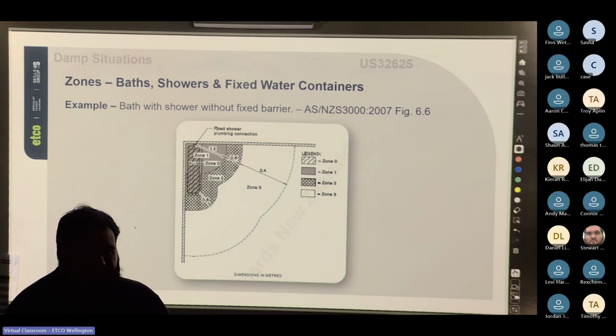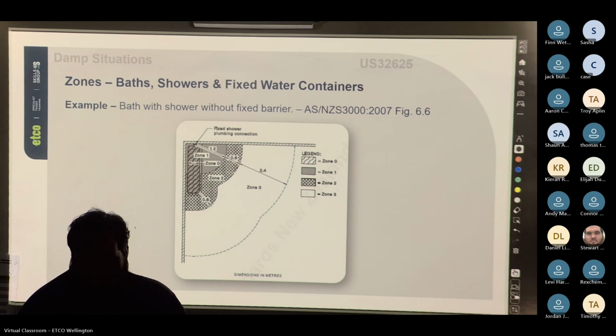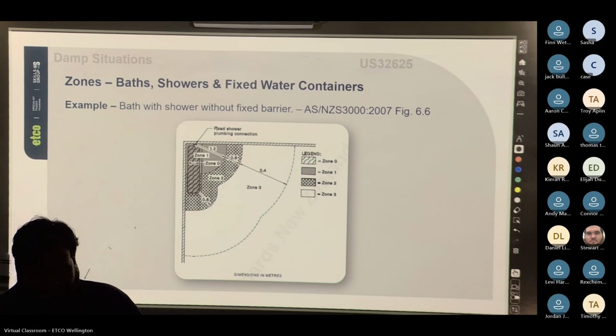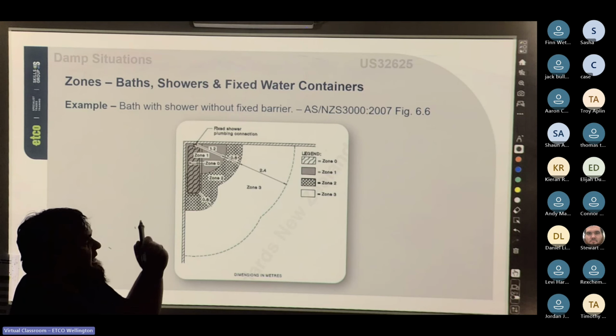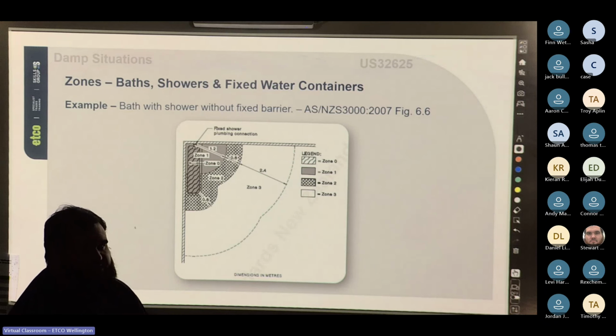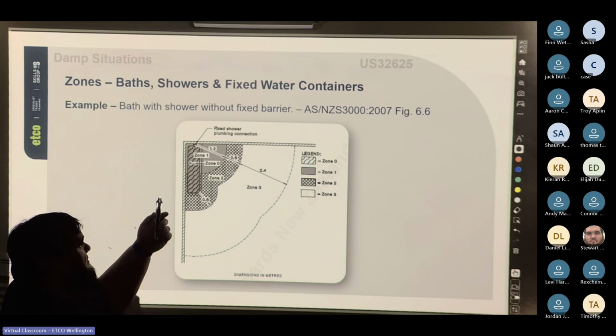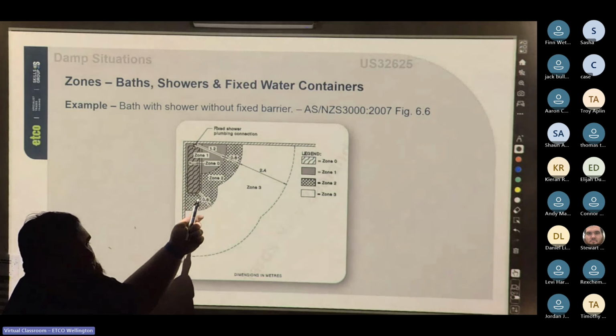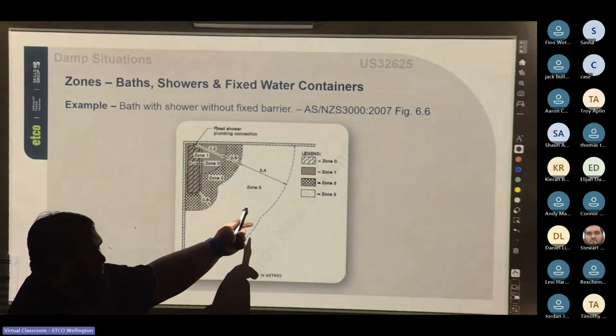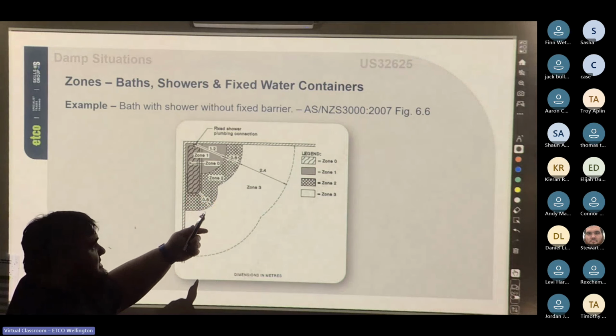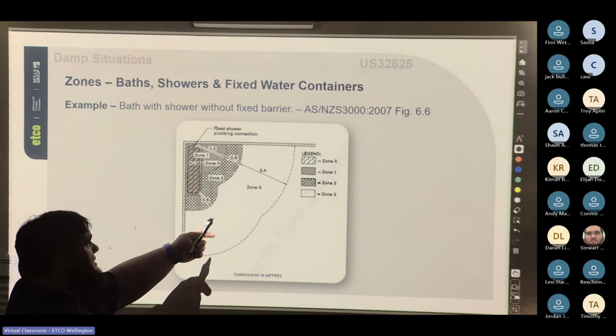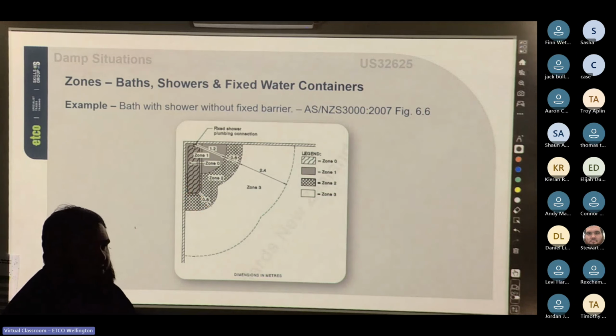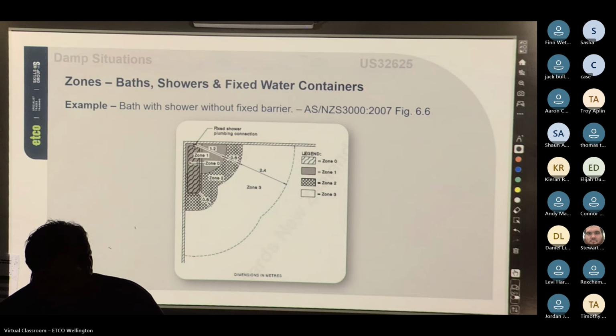So, is anyone confused on anything we've talked about so far? It is quite a big topic, but once you get the hang of one and read over it a few times, it starts to make sense. Basically, all it's telling us is that anywhere from zone 1 to zone 2, I'm not really going to put anything. Zone 3 is where I'm going to comfortably put an RCD protected socket or my light switches. But anything too close to the shower or the bathtub, no dice.